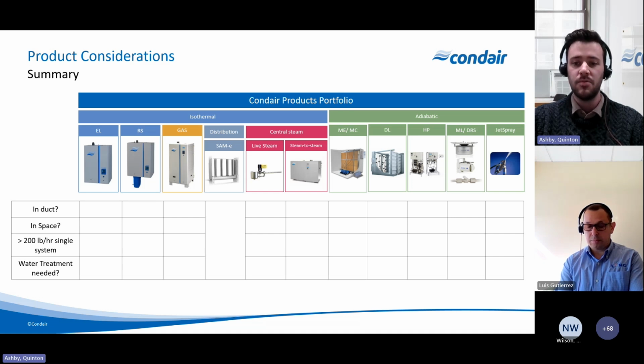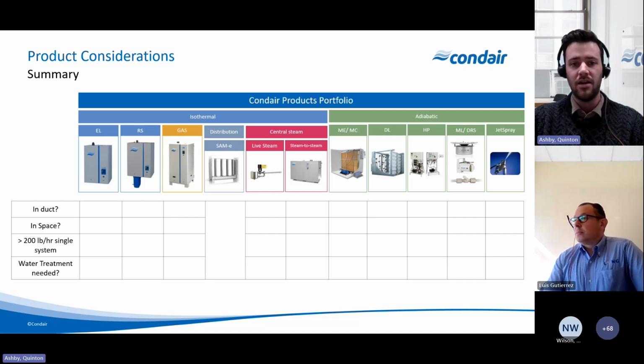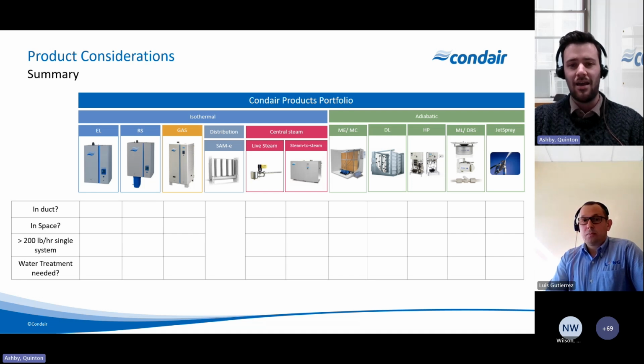We can combine multiple units, but at that point, the electricity needed to generate the steam can start to add up fairly quickly. So we'd want to go with more a gas system, which is usually fairly efficient, or direct boiler steam, which is very efficient because it's already on site. But say we're going past that 200 and we're much higher, almost all of our adiabatic systems do cover that high range except for the jet spray. And this is when you would really want to start to look at an adiabatic solution more than isothermal.